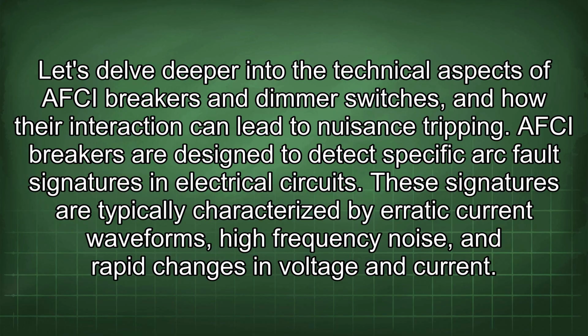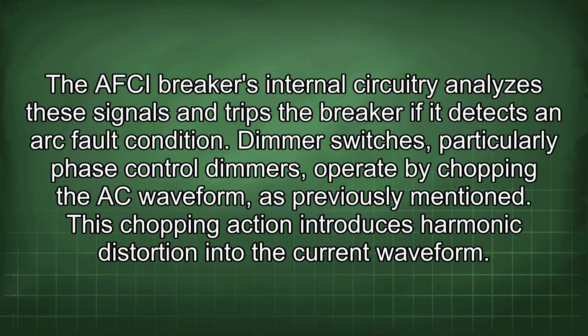Let's delve deeper into the technical aspects of AFCI breakers and dimmer switches, and how their interaction can lead to nuisance tripping. AFCI breakers are designed to detect specific arc fault signatures in electrical circuits. These signatures are typically characterized by erratic current waveforms, high-frequency noise, and rapid changes in voltage and current. The AFCI breaker's internal circuitry analyzes these signals and trips the breaker if it detects an arc fault condition.